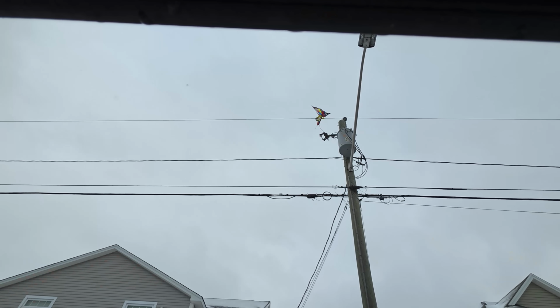So there's no point in me opening the transformer because it's above the switch. It could kill the primary. That's going to dump. Jeez, that'd be over 100 customers. If I have to, safety comes first. Obviously, if I got to shut off the power, I got to shut off the power. But I don't think I'll have to. I should be able to remove that while everything's energized. We'll use some tested hot sticks and gloves and get that kite off the lines on this cold, miserable morning.